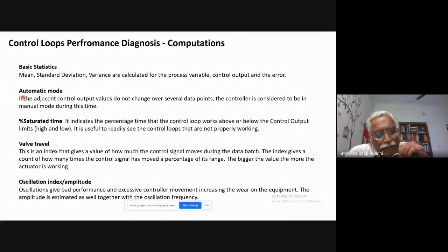What it does is, if you look at the values of the control output, if they remain constant for a certain amount of time, then it assumes that it is not changing. Like that, in the whole data set, it will see how many times it has remained constant where it is not changing. It will calculate the percent of time, and it says that during this time, the controller is not in automatic mode, but it is in manual mode.